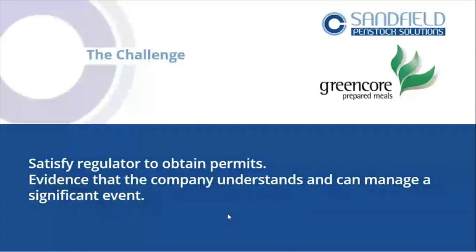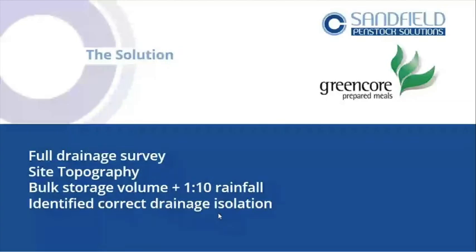Can you contain the loss of an 80-cube bulk storage tank if it's also raining at the same time? What we did — and this is something anyone can do with the right approach — we conducted a full drainage survey to make sure we hadn't missed any outflow point. The whole design is a waste of time if we miss an exit route. Then we looked at isolating the drainage in under 10 seconds at any time to contain a minor spill, then we looked at the site topography to evidence we can contain the event.